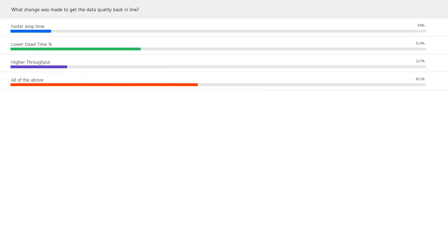And this is great. Most everybody is paying attention. All of the answers are in fact correct, but the all of the above answer is the most complete and comprehensive one. And that is that all of these were done. So the user, these were our interns last year, switched to a faster amp time, which then gave them a lower dead time and also provided higher throughput of the X-ray counts per second that were making their way into the spectrum.